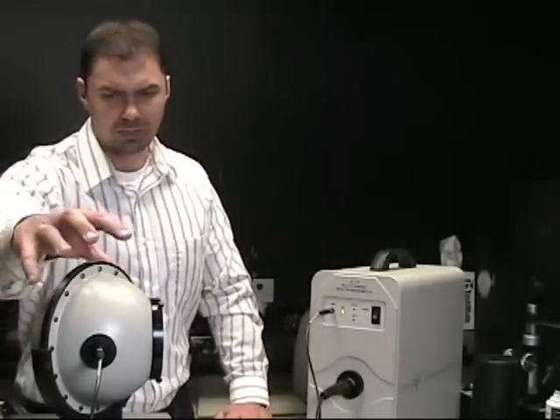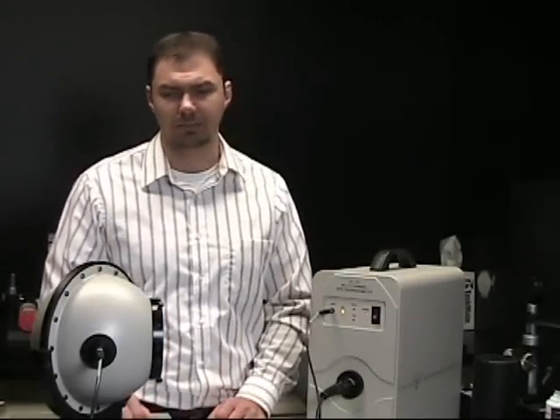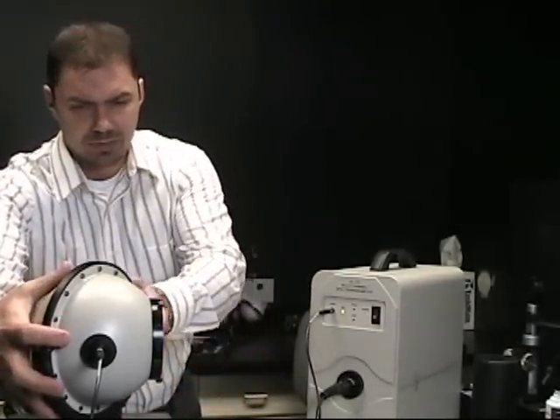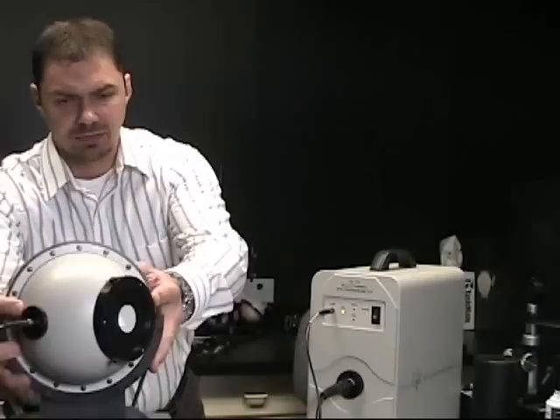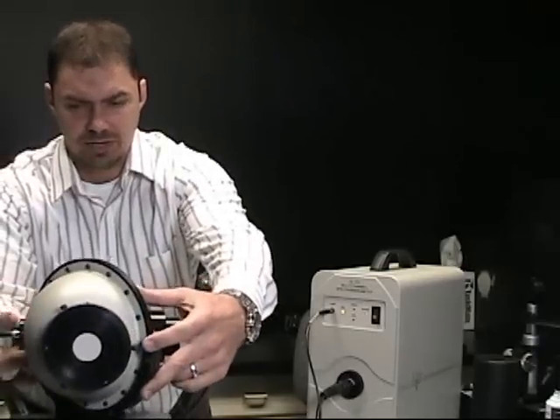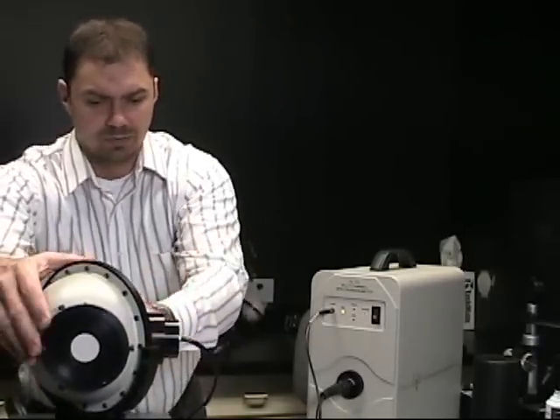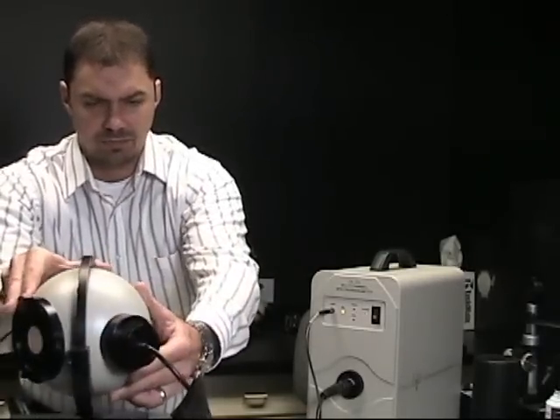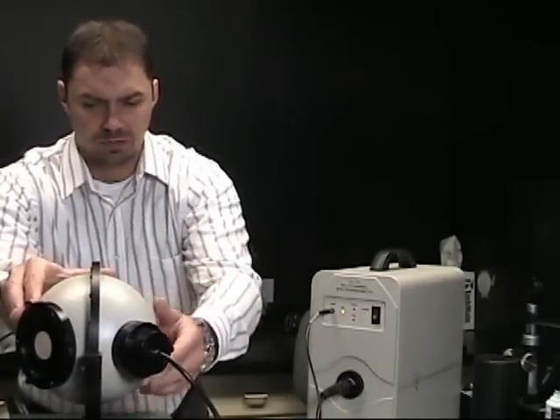To begin with, we're going to do the radiant intensity measurements and the total luminous flux measurements, both with the same input output. We're going to use our 6 inch integrating sphere to do that, and we're configured right now for either irradiance, radiant intensity measurement, or total luminous flux measurement.